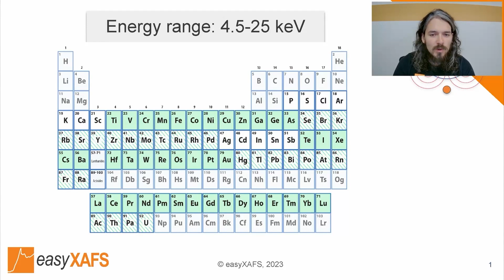In terms of how the samples are prepared, the most common method for solid samples is to grind a powder and mix with a binder to press into a pellet. The pellets are typically sealed with Kapton tape and then mounted up in the instrument. In this picture, you can see a sample wheel with different positions that you can mount different samples in. The sample pellets can be taped up or held on with these magnetic holders.